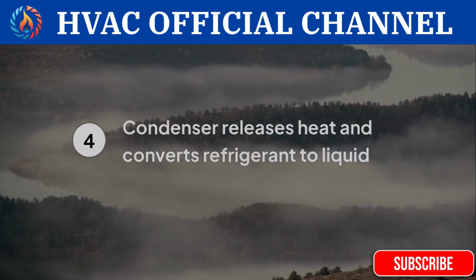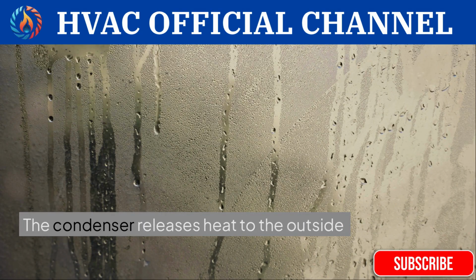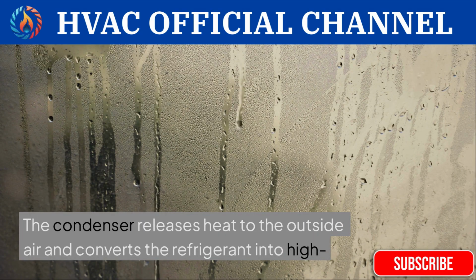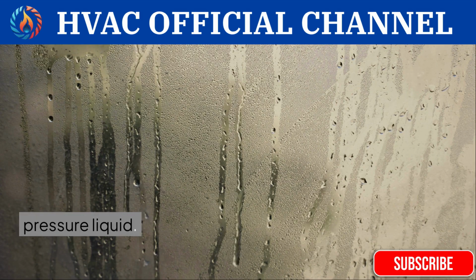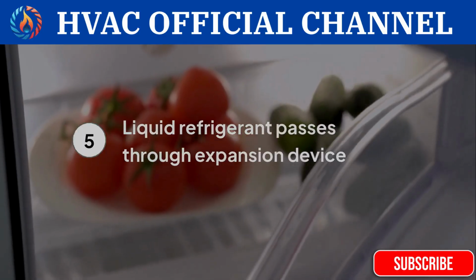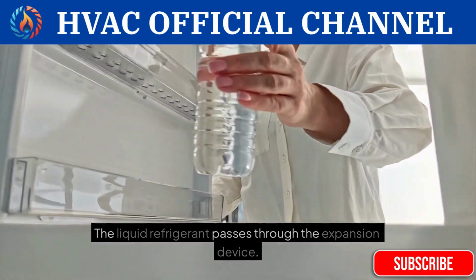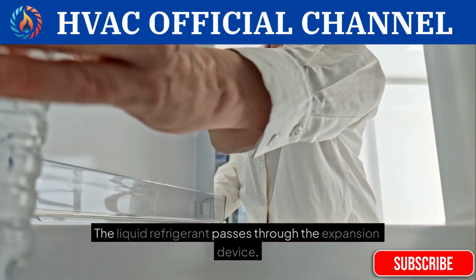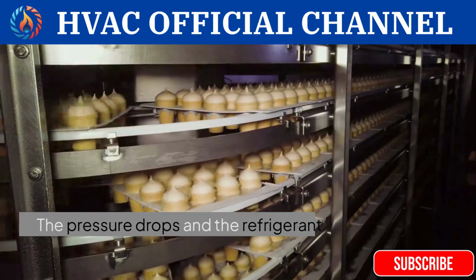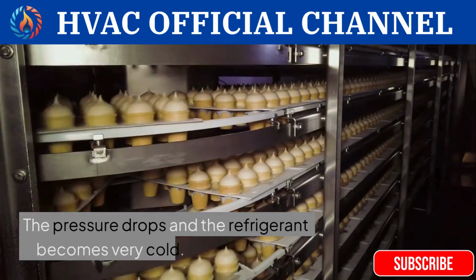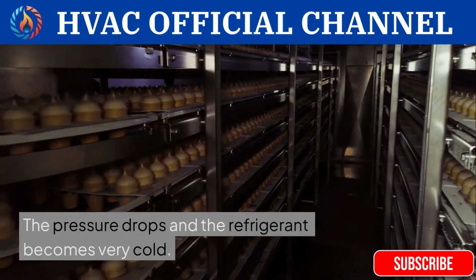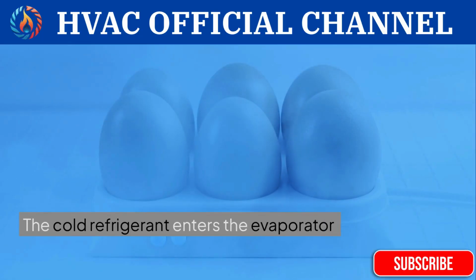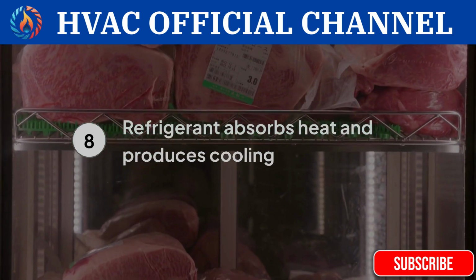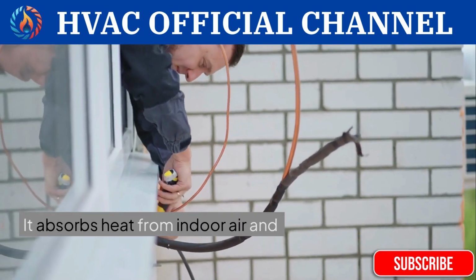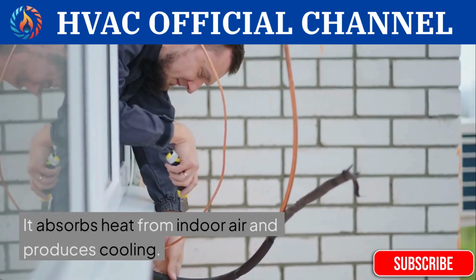Step 4. The condenser releases heat to the outside air and converts the refrigerant into high-pressure liquid. Step 5. The liquid refrigerant passes through the expansion device. Step 6. The pressure drops and the refrigerant becomes very cold. Step 7. The cold refrigerant enters the evaporator coil. Step 8. It absorbs heat from indoor air and produces cooling.